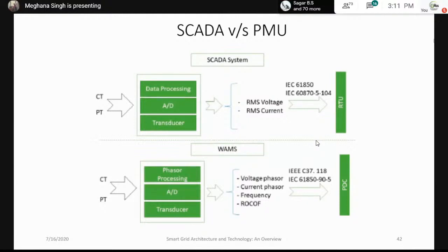So it is connected to a phasor data concentrator. In case of SCADA, it is the RTU. Here it is the PDC. So you take CTs and PTs: RMS voltages and currents are there in SCADA, and in case of WAMS, the phasors are there. Next slide, please.